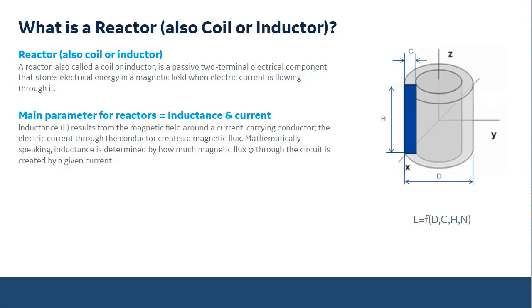The voltage will impact the insulation of the material that goes between the turns. Voltage impacts also the size, the clearances outside the surface of the reactor, and the BIL, basic impulse level, and so on. The power rating depends basically on the current and the impedance that flows through the coil, so it can be calculated based on that. More power means a higher magnetic field. The application is basically, why do we need the reactors? Are we going to use them to limit current? Are they working as a filter? Or maybe are we putting this on an HVDC line to smooth the current? So the application will tell us a lot about how we design safety margins and how they look.